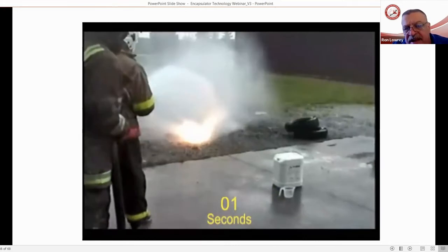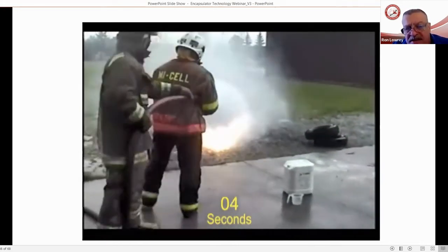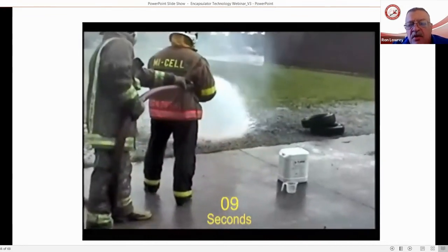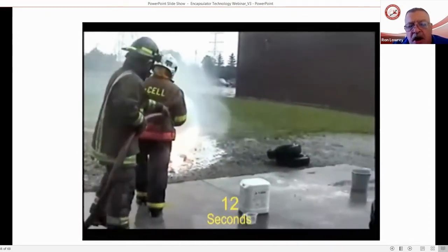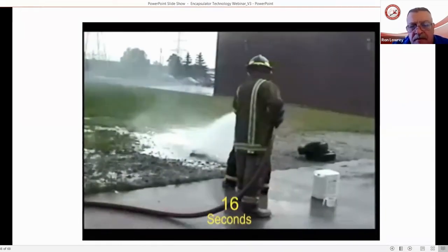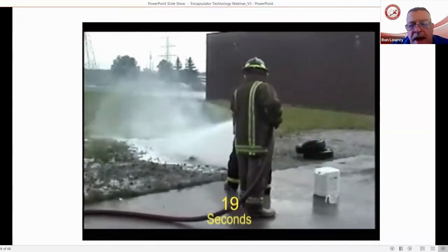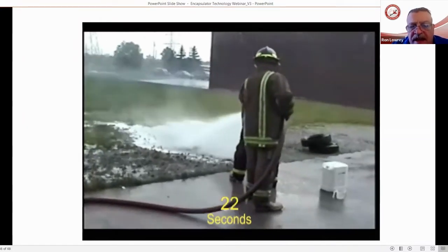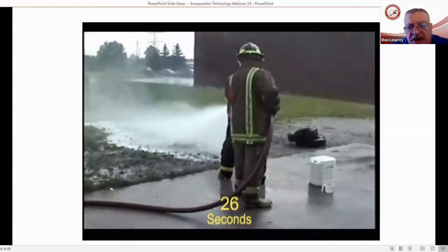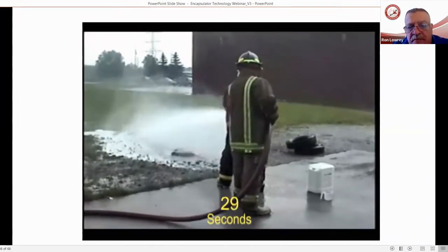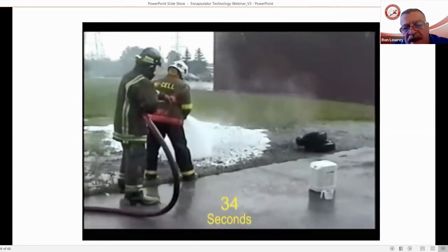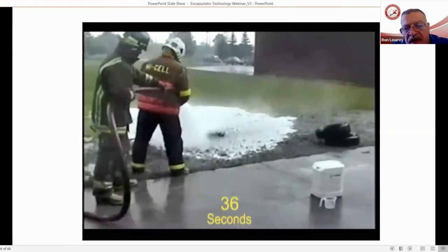So you're seeing here the application technique, kind of like we had with that water mist extinguisher. With a Class D metal, we want to use a dispersed pattern. We want to start by kind of raining down on top of that Class D metal, start to pull some of the heat out. Again, if we remember, those micelles were rapidly absorbing the heat, transferring that heat energy to the solution, to those micelles within the solution. As you can see now, we've got it cooled from that burning white hot to more of an orange. He's now using a more direct application to finish suppression of that fire.